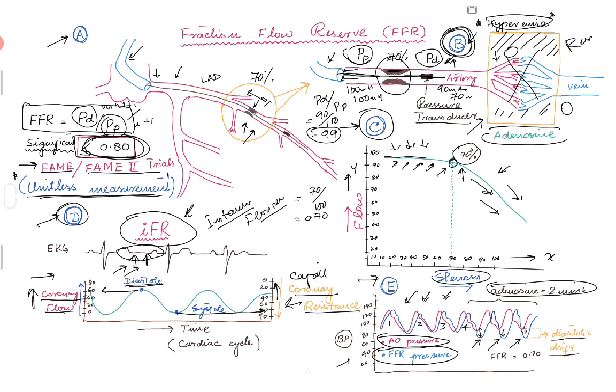It averages it over one, two, three beats, and it's basically looking at these R waves to kind of decide when it has to take that measurement. I won't go into detail what are the numbers for the IFR. Every vendor has validated that across with the FFR, and they give you a number. If it reaches that number, that is significant.